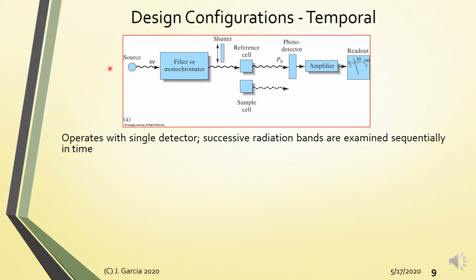Or zero instrument. When you zero the instrument while the shutter is closed, you are canceling what you call the dark current. Dark current is the reading in the detector in the absence of radiation, and this is due to the nature ng electronic circuit for the detector. After that step, you release the shutter.